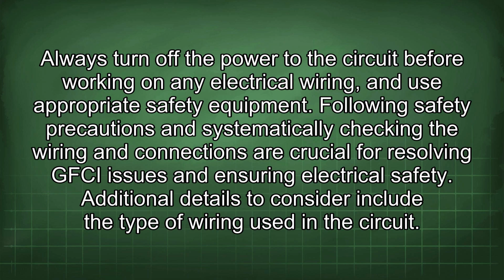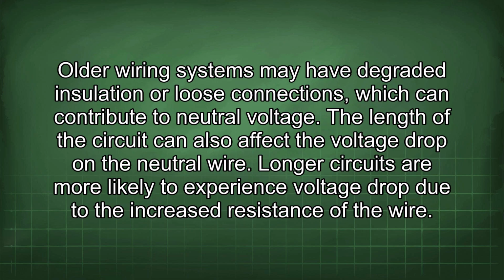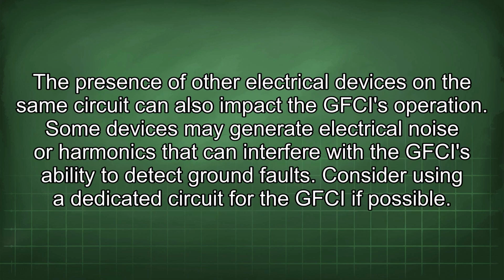Additional details to consider include the type of wiring used in the circuit. Older wiring systems may have degraded insulation or loose connections, which can contribute to neutral voltage. The length of the circuit can also affect the voltage drop on the neutral wire. Longer circuits are more likely to experience voltage drop due to the increased resistance of the wire. The presence of other electrical devices on the same circuit can also impact the GFCI's operation. Some devices may generate electrical noise or harmonics that can interfere with the GFCI's ability to detect ground faults.